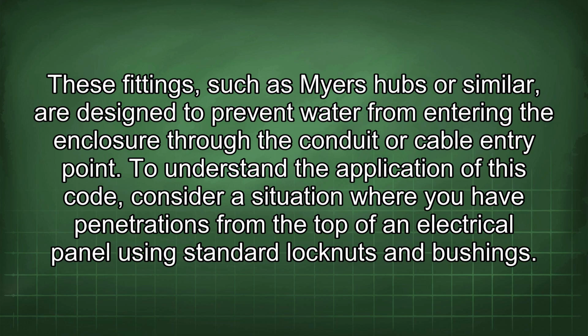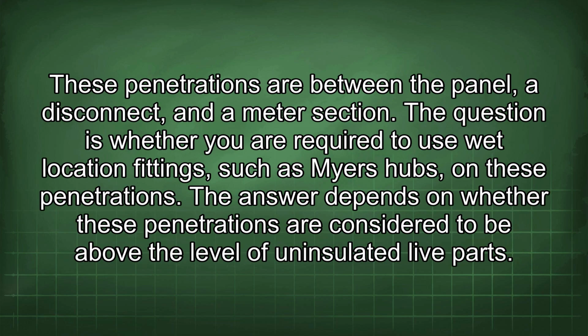To understand the application of this code, consider a situation where you have penetrations from the top of an electrical panel using standard lock nuts and bushings. These penetrations are between the panel, a disconnect, and a meter section. The question is whether you are required to use wet location fittings such as Myers hubs on these penetrations. The answer depends on whether these penetrations are considered to be above the level of uninsulated live parts.